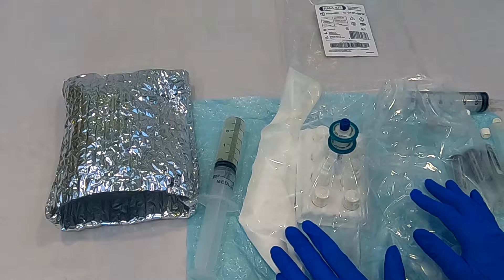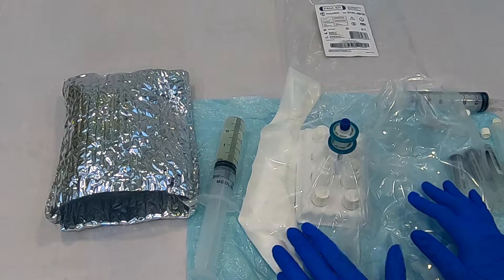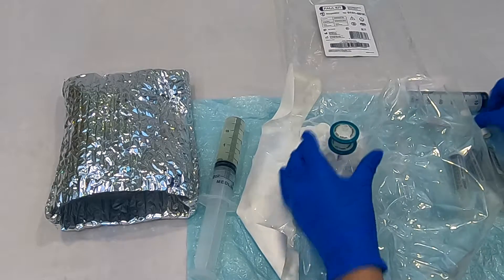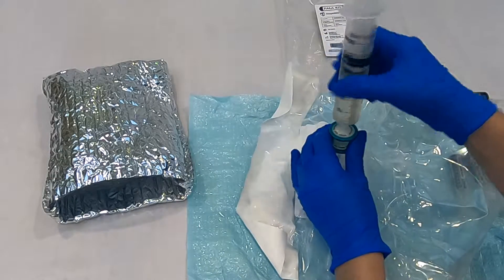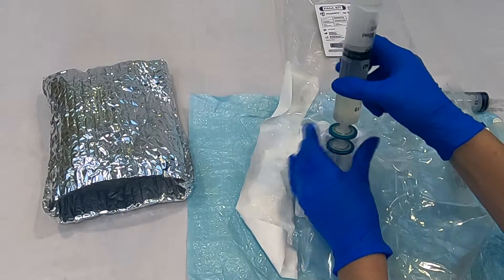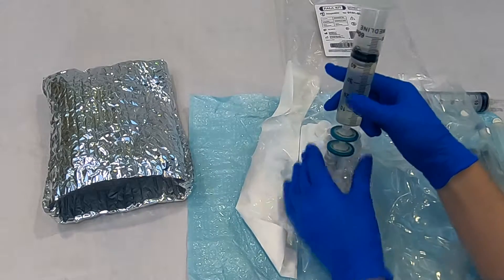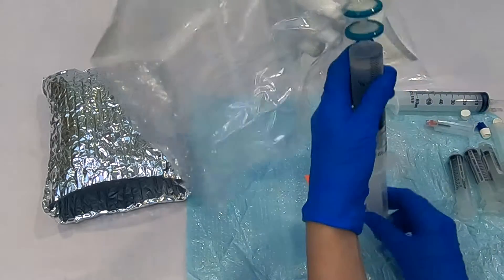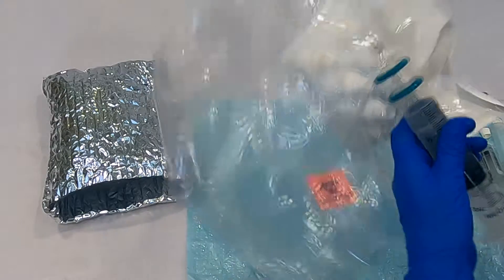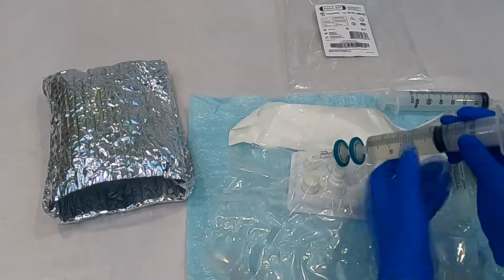Center the tray directly under the 0.2 micron filter and tent the bag as shown. Remove the filter cap from the proximal filter and attach the filled syringe to the filter. Prime the filter by pointing the dispensing end upright and dispensing liquid from the attached syringe in the same manner a syringe is primed.